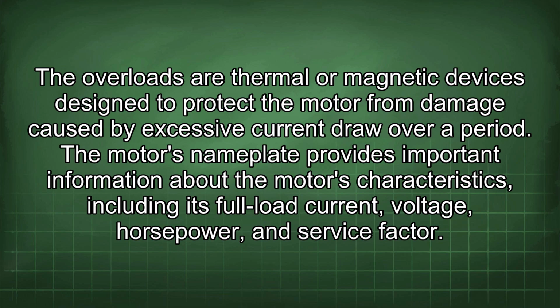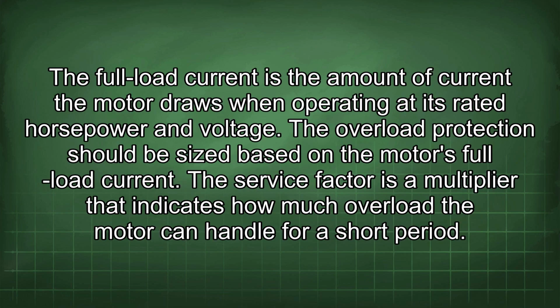The overloads are thermal or magnetic devices designed to protect the motor from damage caused by excessive current draw over a period. The motor's nameplate provides important information about the motor's characteristics, including its full load current, voltage, horsepower, and service factor. The full load current is the amount of current the motor draws when operating at its rated horsepower and voltage. The overload protection should be sized based on the motor's full load current.